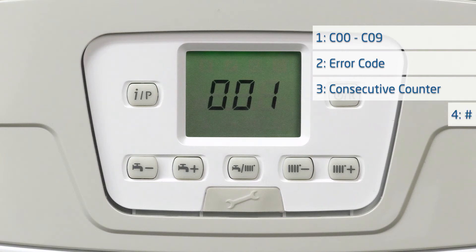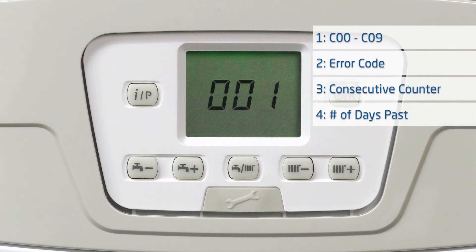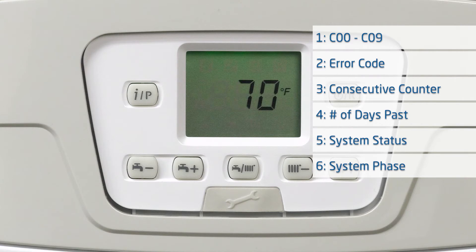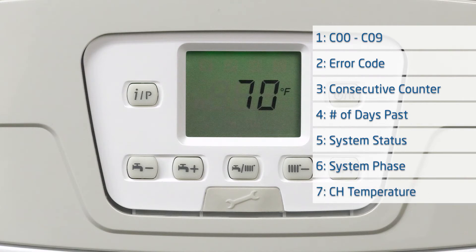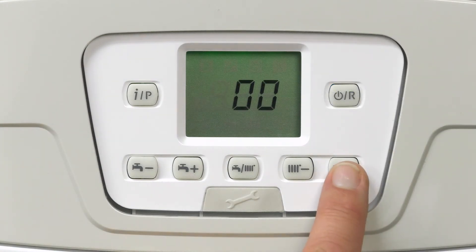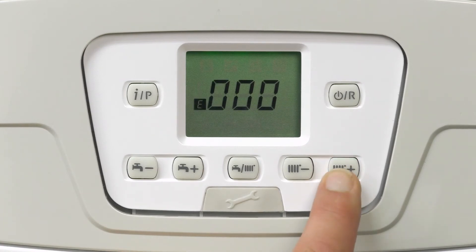The fourth number tells you how many days have passed since the error. The next number is the system status, followed by the system phase, and finally the temperature of the boiler at the time that the error code occurred. I can then press the radiator plus button to advance to the next error code, C01, and it will show the seven different numbers for that error.